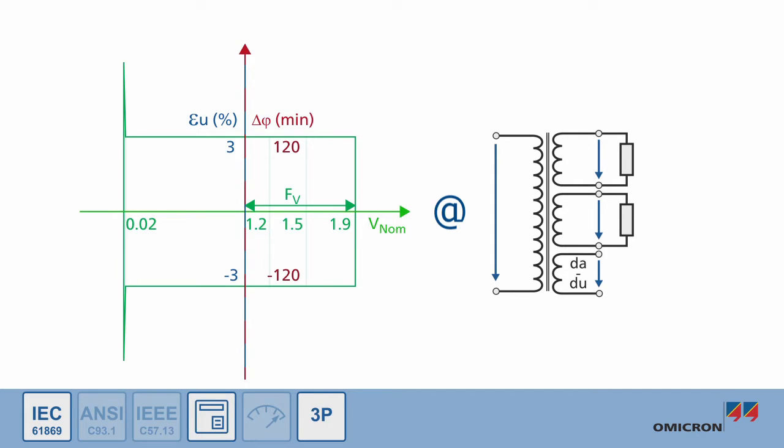During these tests, a residual voltage winding should be unloaded for tests up to nominal voltage. During tests with nominal voltage multiplied by the rated voltage factor, the residual voltage winding should be loaded with the rated burden.